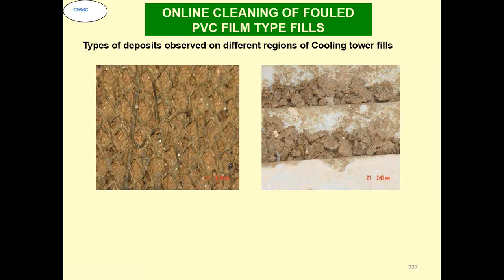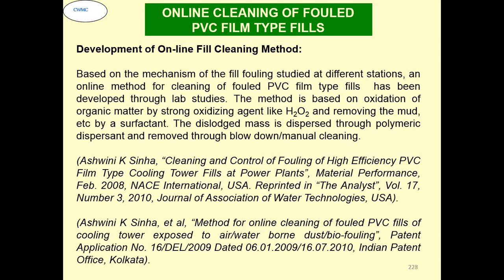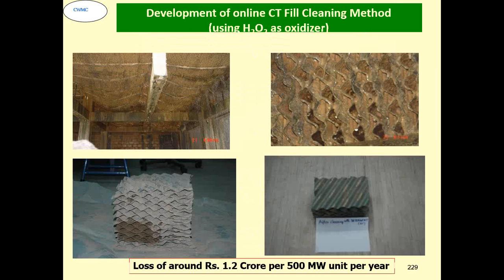This is the kind of fouling which is there. It mostly consists of mud, dust or dirt, whatever is there in the system. So we developed this cleaning method in the lab. This was the kind of fill pack that we had received. We developed the method using hydrogen peroxide, and this is the clean film that you are seeing.